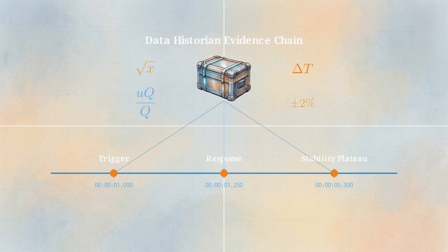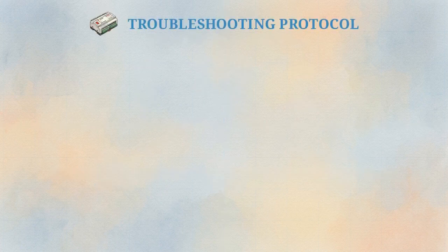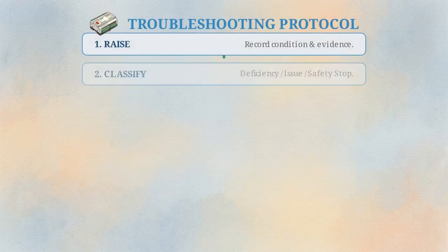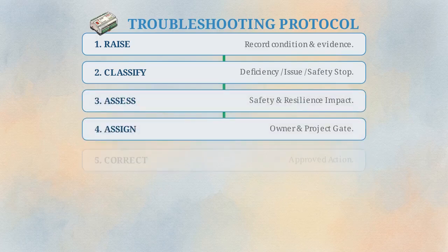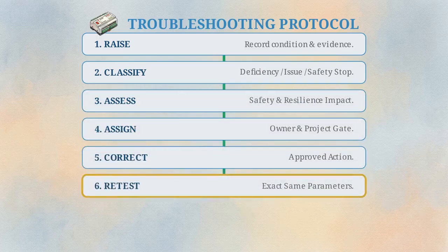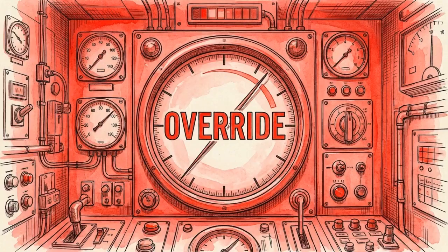When a test fails, operators follow a strict troubleshooting protocol. The issue is raised, classified, assessed, assigned, corrected, retested under the exact same parameters, and finally closed. In extreme life safety edge cases like NFPA fire and smoke scenarios, the system totally ignores standard BMS software speed reductions. Under the emergency run-to-destruction mandate, fire alarm matrices force smoke exhaust fans into hardwired bypass loops, prioritizing life safety above the survival of the fan motor and ignoring thermal overloads.